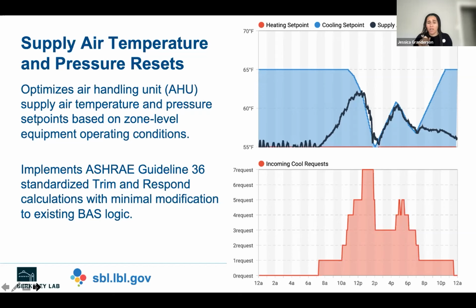Between that 2 like afternoon period, you see a little bit of modulation of those temperatures in response to the fluctuation in cooling requests. And then you see the corresponding response at the end of the day as the cooling requests drop off, and we again rise back to those unoccupied conditions.